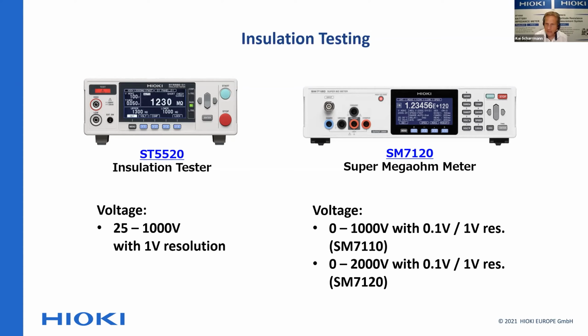SM7120 or 7110, if you use the smaller model, which also only goes to 1000 volts, is that you can set the test voltage with a resolution of 1 volt with the ST5520, and you can set that with 0.1 volts with the SM7120. Why is it important to set test voltages at 0.1 volts when you're actually looking at test voltages between 500 and 1000 volts? Actually, for that, it isn't. But you can also use the SM7120 or 7110 at a later stage, to make some tests after the electrolyte has been filled. And in that case, you will use a much lower test voltage.